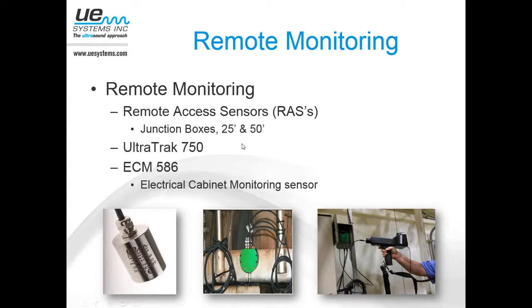We've got what we call a remote access sensor, which lets you mount a sensor internally, and as you can see by this right-hand picture, run the cable out to a junction box and simply take your ultra probe and hook it into the cable coming out, still keeping that on your route. It's no different than actually touching the motor with the magnetic mount. They can be run 25 or 50 feet with no loss of signal.